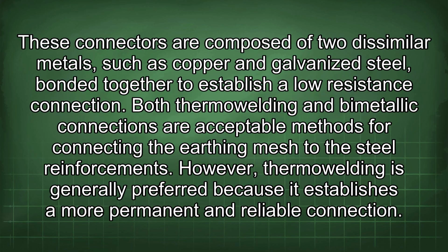These connectors are composed of two dissimilar metals, such as copper and galvanized steel, bonded together to establish a low-resistance connection. Both thermowelding and bimetallic connections are acceptable methods for connecting the earthing mesh to the steel reinforcements. However, thermowelding is generally preferred because it establishes a more permanent and reliable connection.